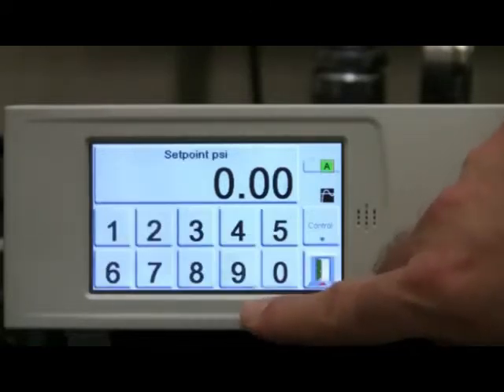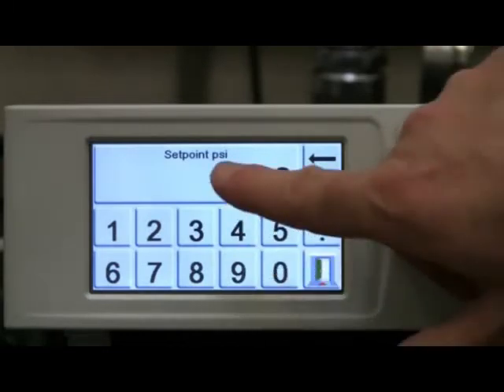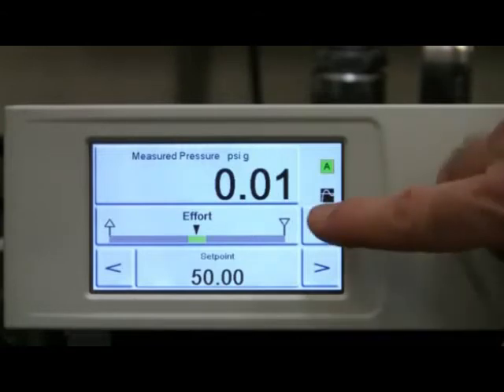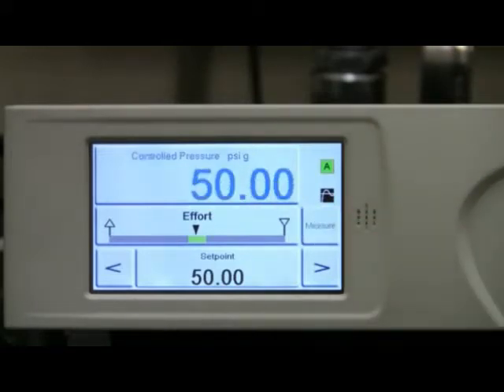Next, we will enter 50 psi as the first set point pressure using the numeric keypad, and then select control to change the PACE 5000 from measure mode to control mode. Notice how fast the PACE 5000 control to 50 psi. Once the set point is achieved within user defined limits, the color of the pressure display will change from blue to green, providing immediate feedback to the operator that the reading from the device under test can now be recorded.